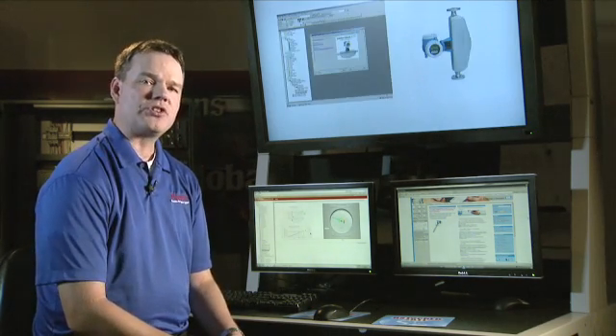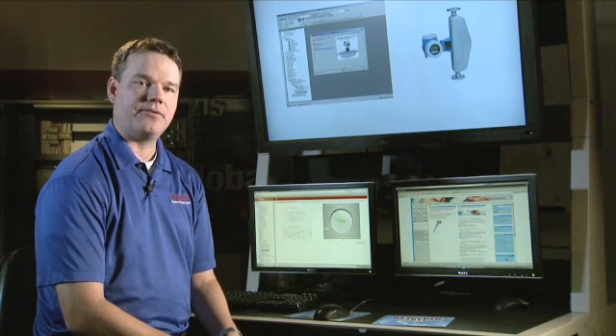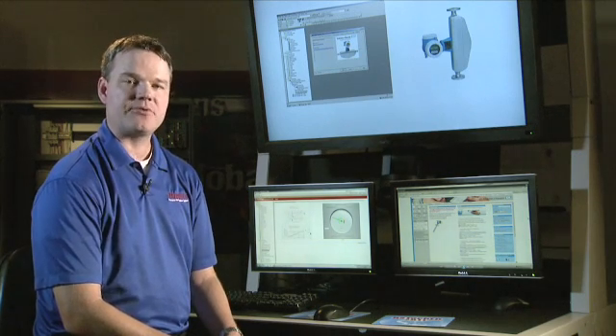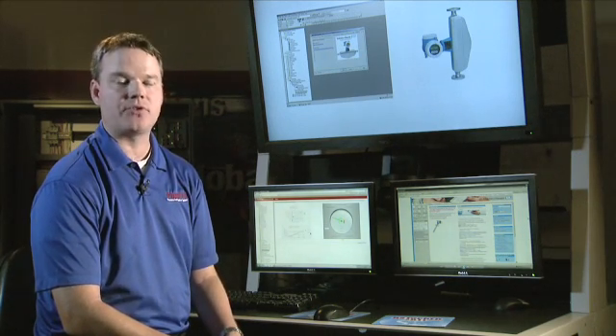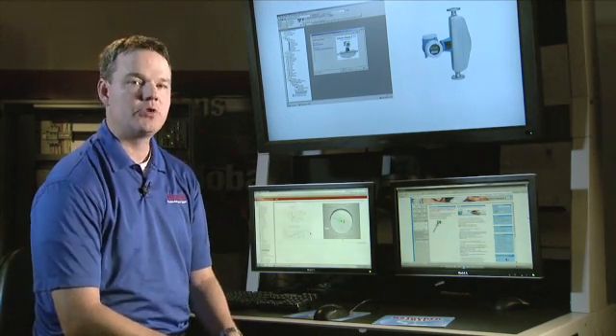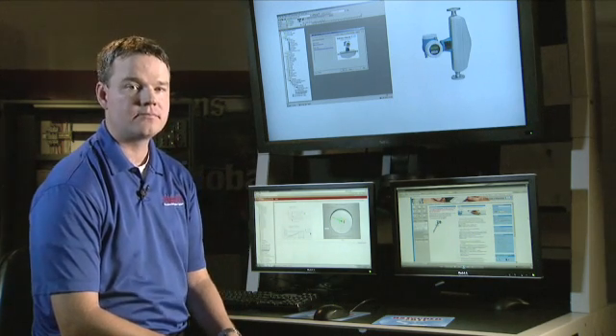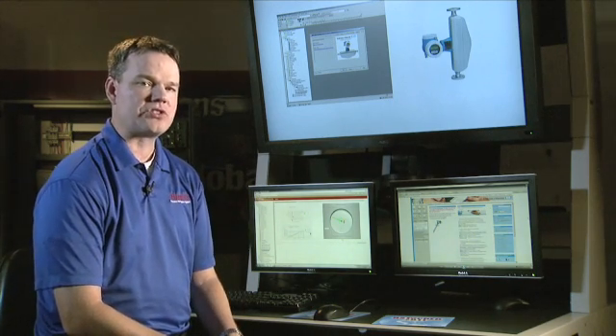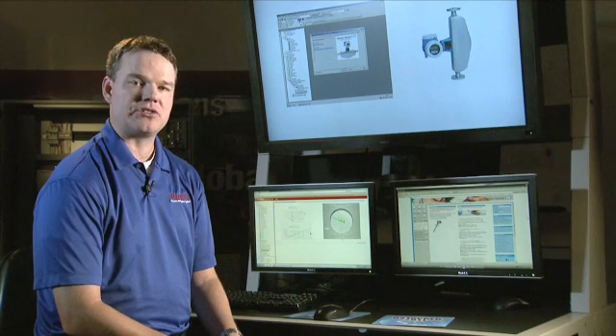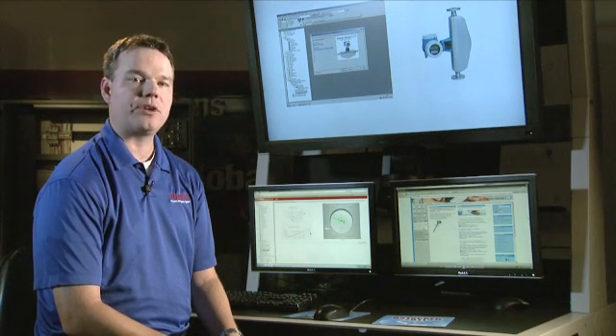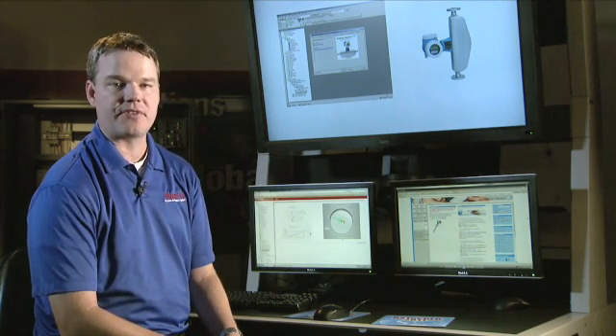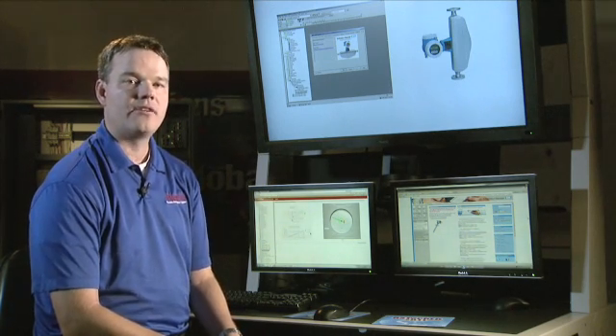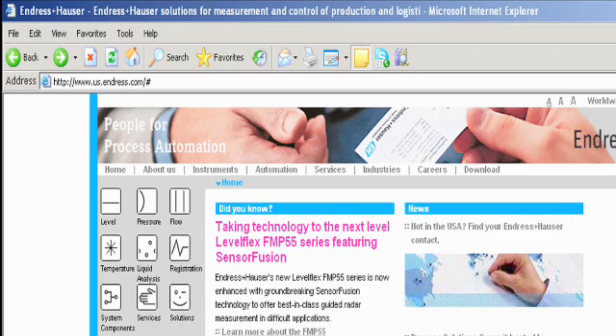I'm going to show you how to add and configure an Endress+Hauser Coriolis mass flow meter to a Rockwell Automation PlantPAX system. Before you start, you'll need to download and install the free add-on profile for Logix 5000 from the Endress+Hauser website. The website address is us.endress.com.